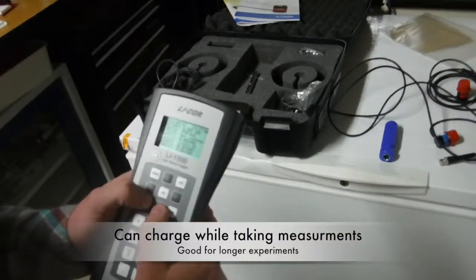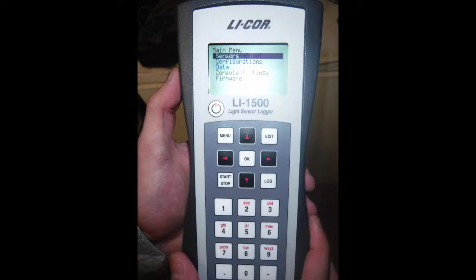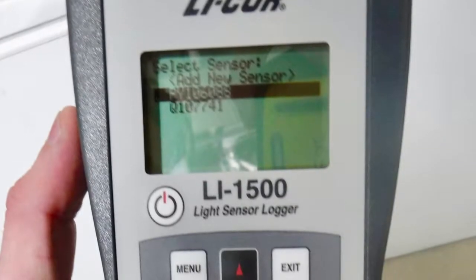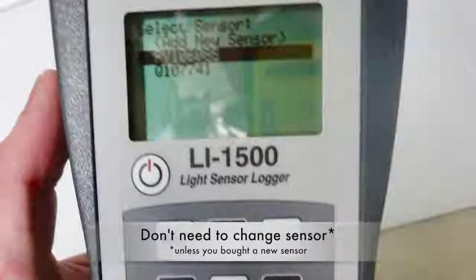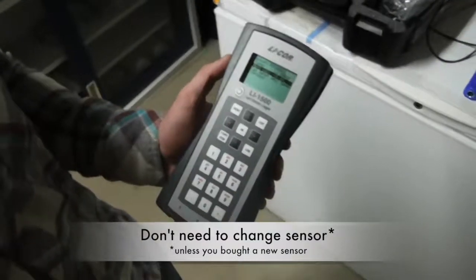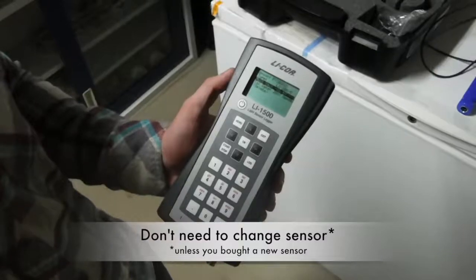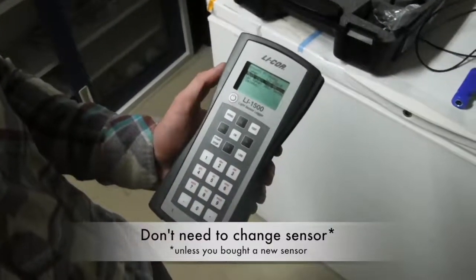When you first turn it on, you should see a main menu like this. If you press menu, from the main menu here, the first option is sensors. There's not much you should have to be doing on this unless there's a new sensor that's purchased for the lab. Right now you can already see they have the pyranometer as well as the quantum meter. Basically it has the multiplier value as well as the calibration date, specifically for when that unit was calibrated.